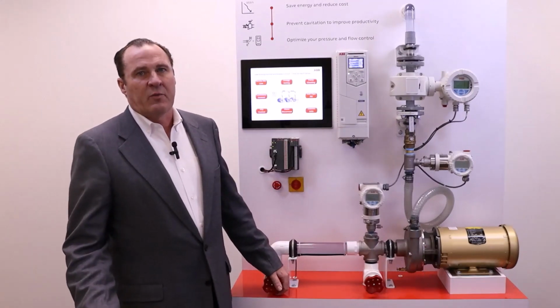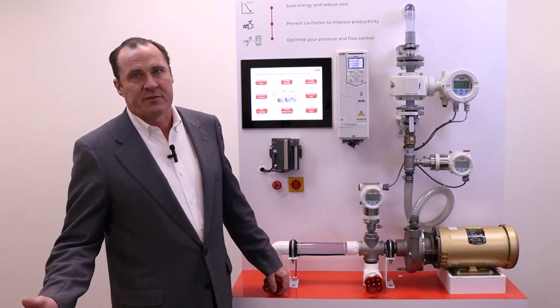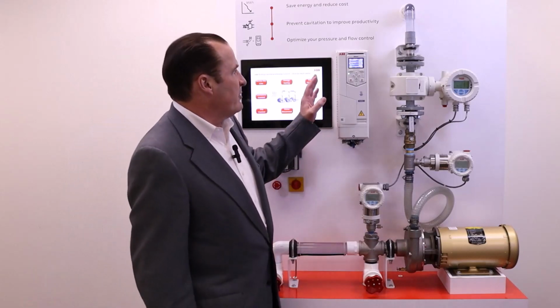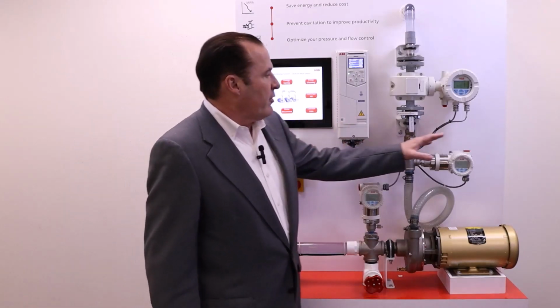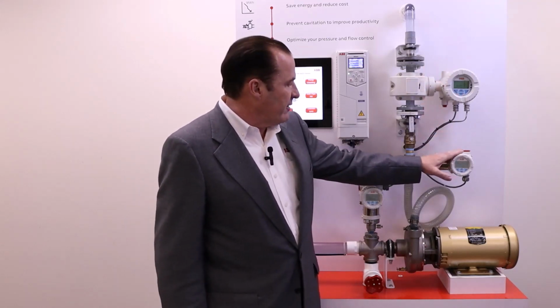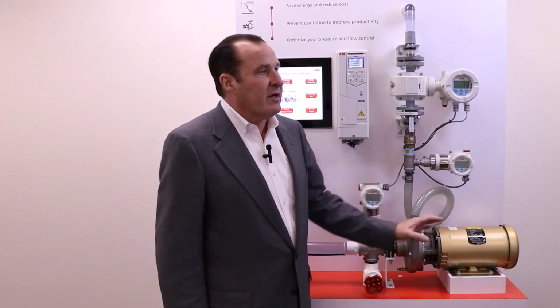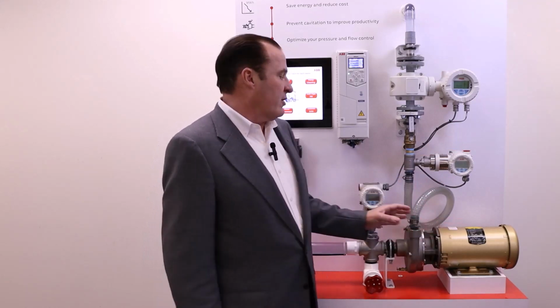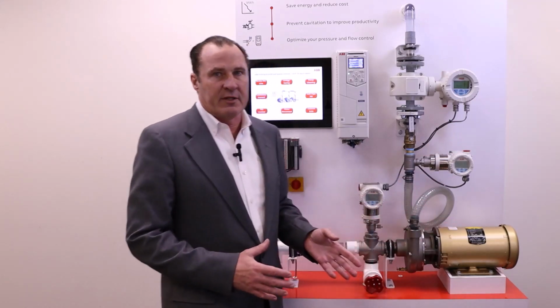Now let's take a look at what it takes to set up sensorless control. Sensorless pump control requires pressure and flow. We have a magnetic flow meter, we have an output pressure meter here, we have our pump with our motor combination. So we are going to do the testing of the pump and motor combination.